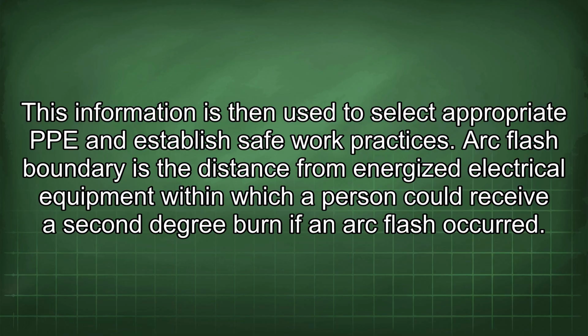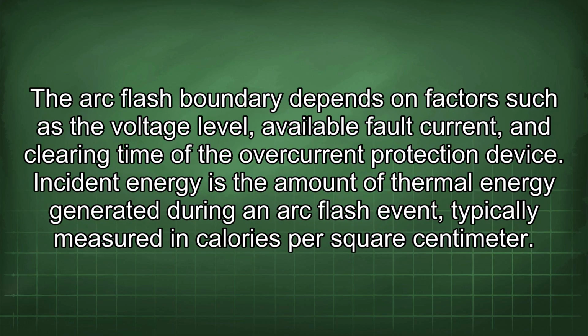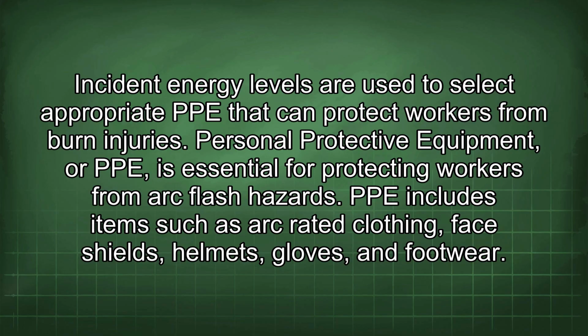Arc flash boundary is the distance from energized electrical equipment within which a person could receive a second-degree burn if an arc flash occurred. The arc flash boundary depends on factors such as the voltage level, available fault current, and clearing time of the overcurrent protection device. Incident energy is the amount of thermal energy generated during an arc flash event, typically measured in calories per square centimeter. Incident energy levels are used to select appropriate PPE that can protect workers from burn injuries.